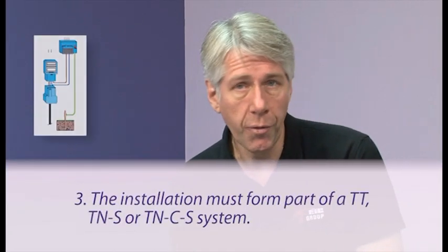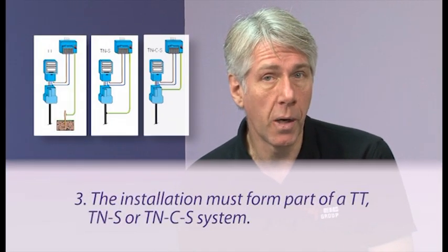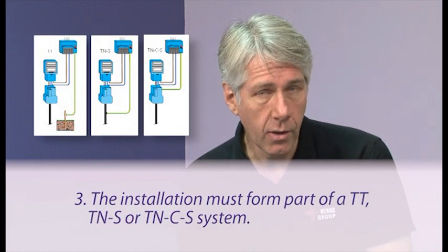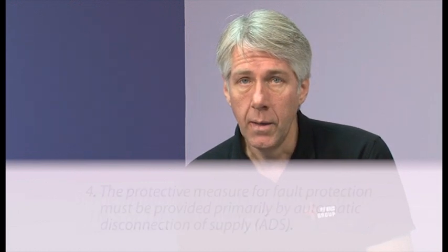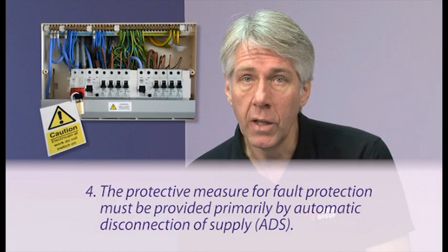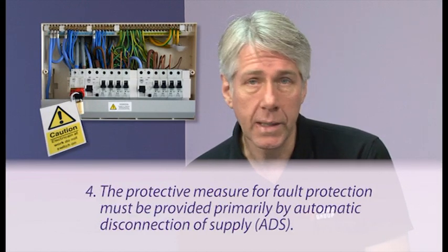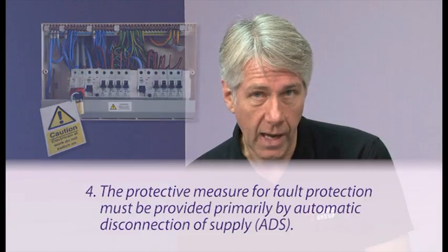The third and fourth requirements are that the installation forms a part of a TT, TN-S or TN-C-S system, and that the protective measure for fault protection is provided primarily by automatic disconnection of supply, ADS. And moving on to the minor domestic electrical installation work certificate, for what types of work should this be used? The minor work certificate may only be used for an addition or an alteration to a single circuit that does not extend to the provision of a new circuit.